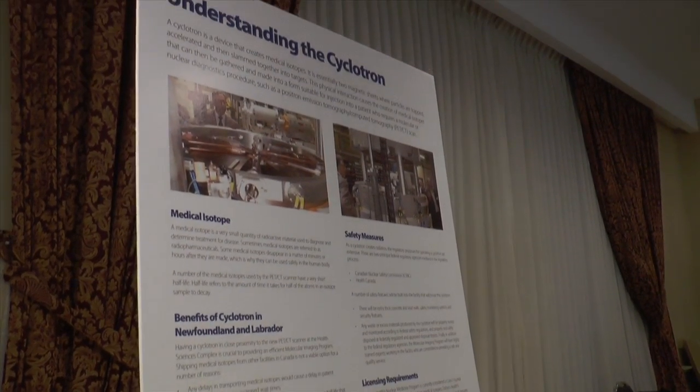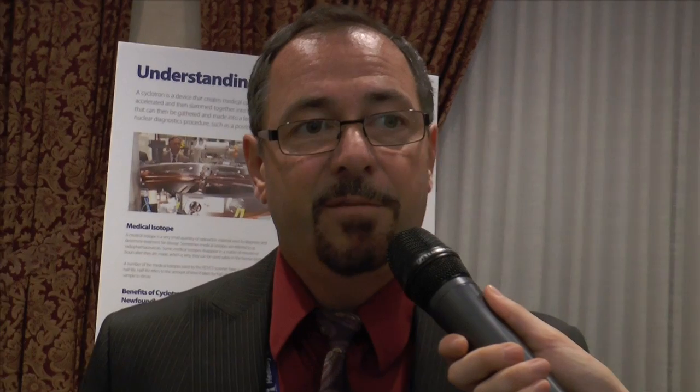The problem with bringing isotopes in is, number one, our weather. Even bringing in existing isotopes, we're challenged almost monthly with delivery problems. We don't have hospitable weather and transportation can be problematic. It's a radioactive material and it decays — meaning that when you start out with 100% of the PET isotope FDG, in about 110 minutes you're left with 50% of it. So if it doesn't get here quickly, we won't have enough left to use on patients. It's imperative that we produce our own here so we have a supply whenever we need it — enough to do all the patients required in Newfoundland and Labrador.